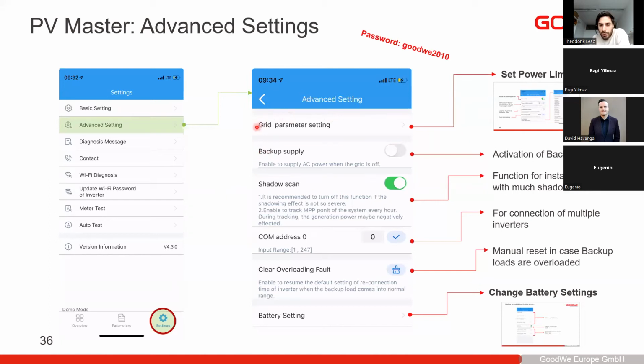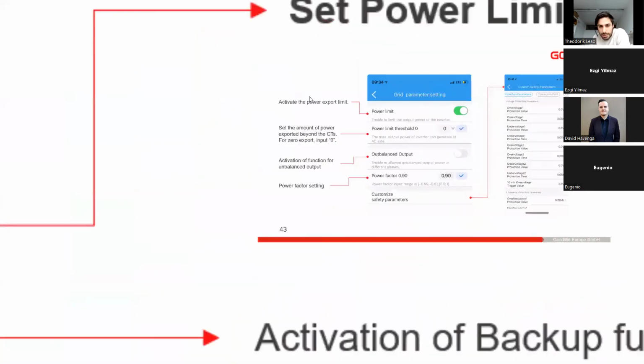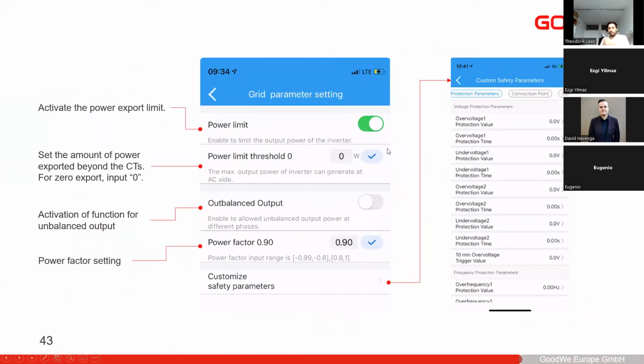First off, we have the grid parameter settings. Let me show you this. Here you can set up the power limit in case you want to limit exported power - tick this box and enter how much you want allowed to be exported to the grid. We also have the unbalanced output function, which you can tick to allow unbalanced output. Here you can change the power factor and customize the safety parameters. As I said before, if you select the standard 50 Hertz and need to set up the settings in a specific way as per what the DNO requests, click on this one and you'll have all the custom parameters to set manually.